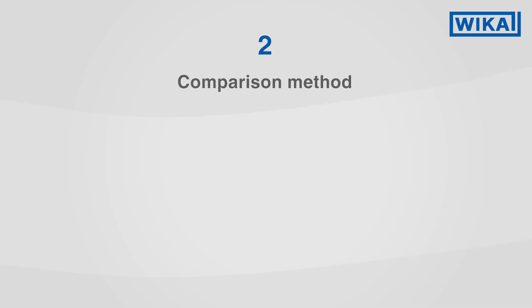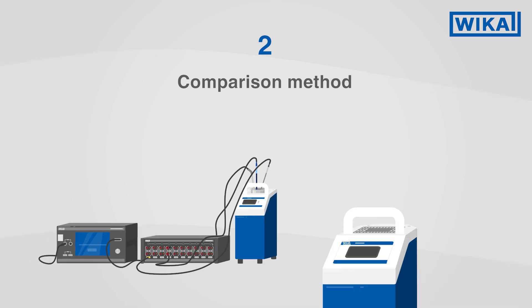With the comparison method, the measured values of the calibration item are compared with a reference thermometer. For this, the test item and reference thermometer are put into a calibration bath, into a dry well calibrator, or into a tube furnace.